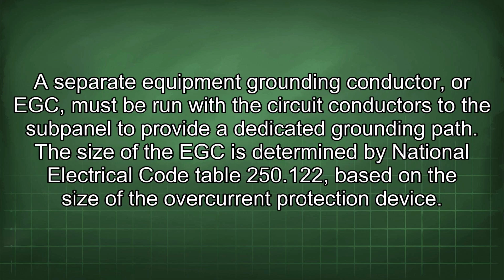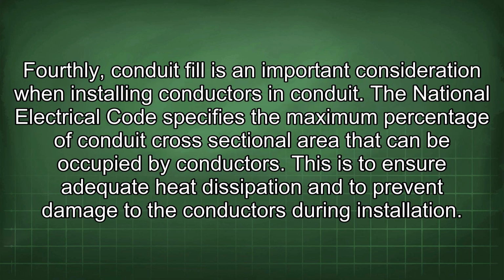A separate equipment grounding conductor, or EGC, must be run with the circuit conductors to the subpanel to provide a dedicated grounding path. The size of the EGC is determined by National Electrical Code Table 250.122, based on the size of the overcurrent protection device. Fourthly, conduit fill is an important consideration when installing conductors in conduit. The National Electrical Code specifies the maximum percentage of conduit cross-sectional area that can be occupied by conductors. This is to ensure adequate heat dissipation and to prevent damage to the conductors during installation.